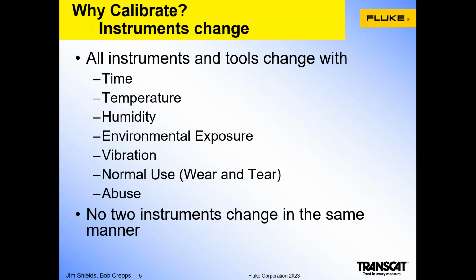And abuse isn't necessarily indicating that someone's not doing their work. It just so happens that in many instances, the processes are very difficult in the instruments that are making measurements of that process. And abuse is just a byproduct of the difficulty in the service in which the devices are installed. The bottom line, though, is no two instruments change in the same manner. And since that change is difficult to predict, these devices do require to be, at the very least, verified that they're accurate, that their performance is within specification, and adjusted in the event that it's not.